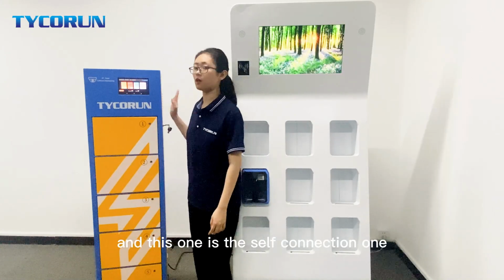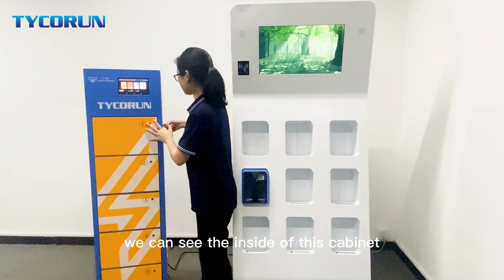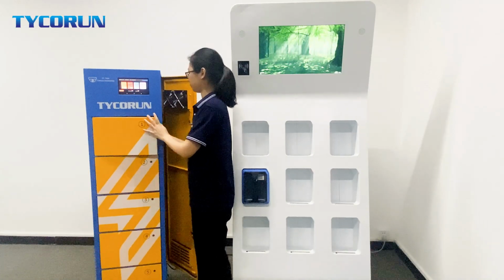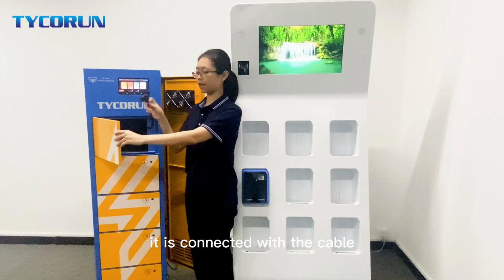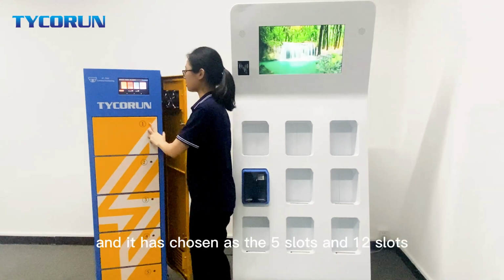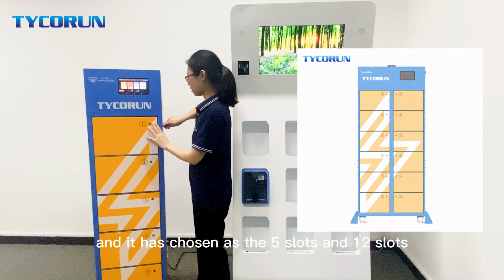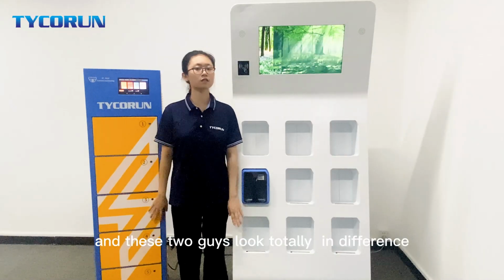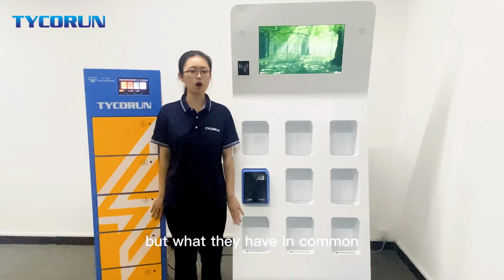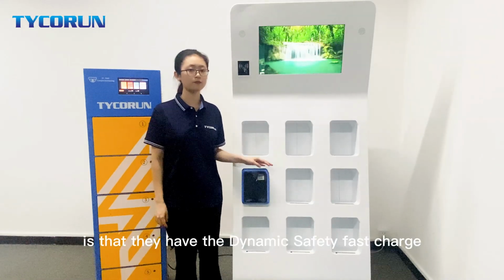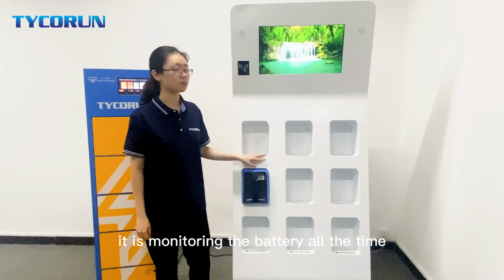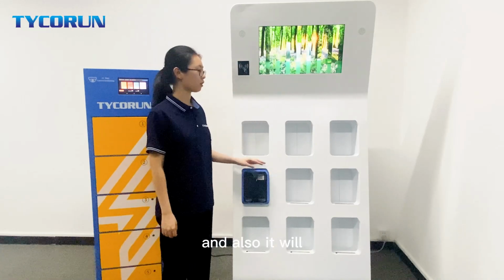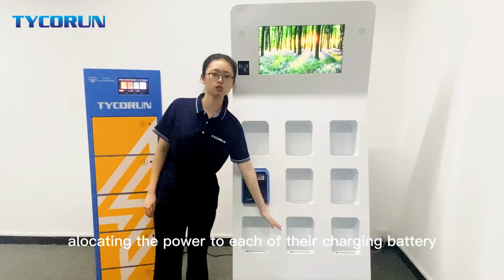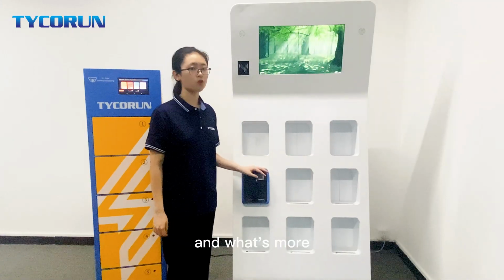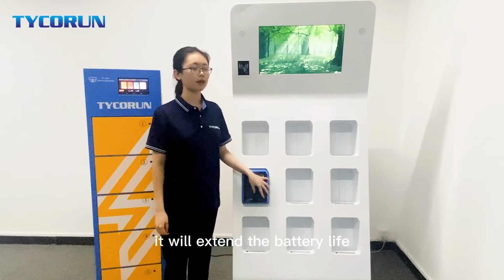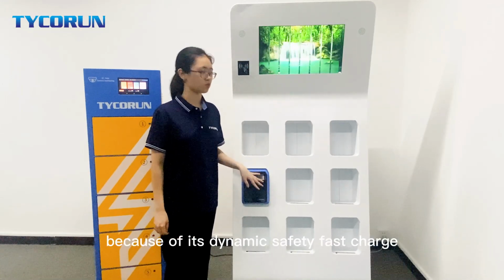And this one is the soft connection one. We can see the inside of this cabinet. It is connected with cables, and it can be chosen as the 5 slots or the 12 slots. And these two cabinets are totally different, but what they have in common is that they have the dynamic safety fast charge, which means that it is monitoring the battery all the time, and also it will allocate the power to each of the charging batteries. And what's more, it will extend the battery life because of its dynamic safety fast charge.